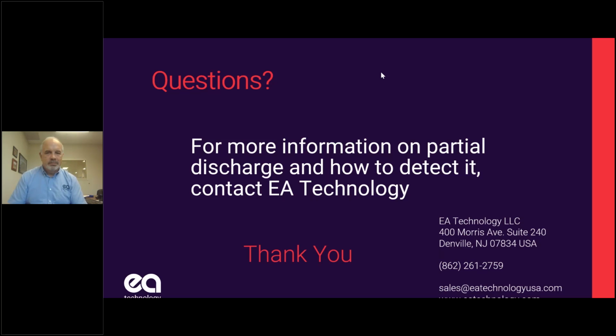Okay. Just more of a comment than a question. Maybe worth mentioning that non-contact volt detectors do not work on the shielded part of the cable. With the cable live, the non-contact detector will show dead if it approaches the shield part of the cable. It might be worth mentioning that if one touches a live termination, you might get shocked or worse.